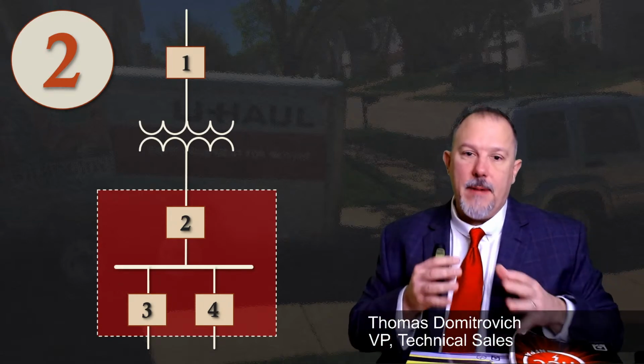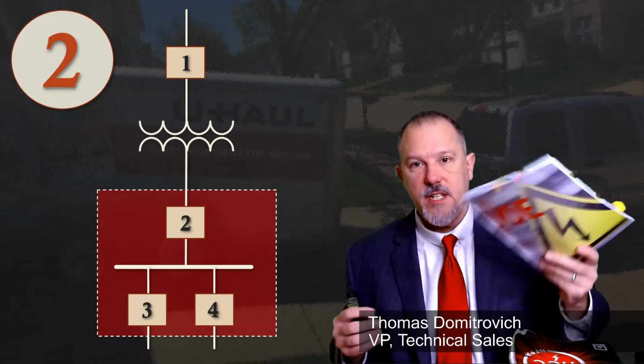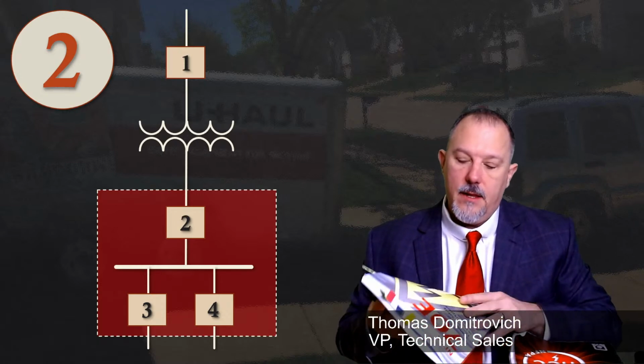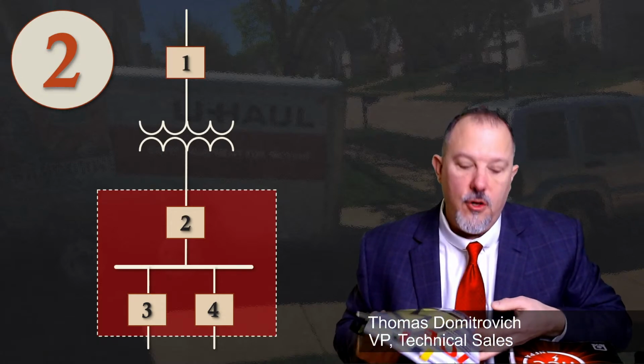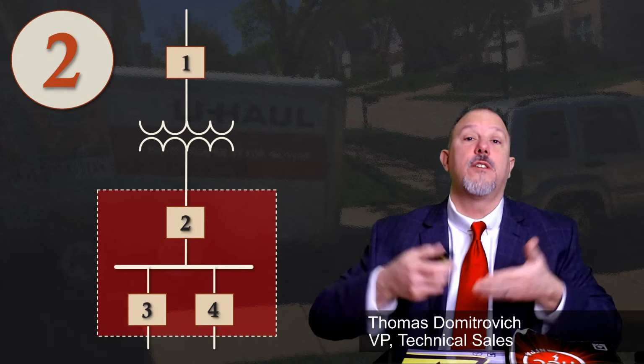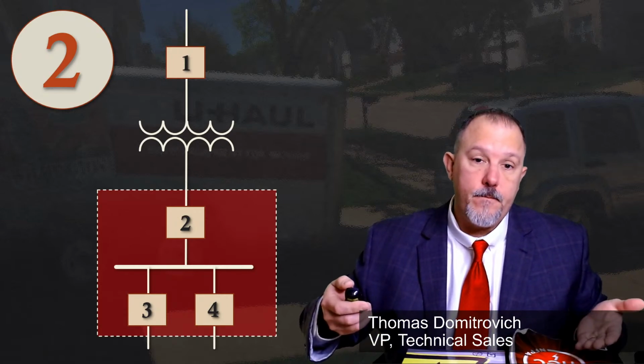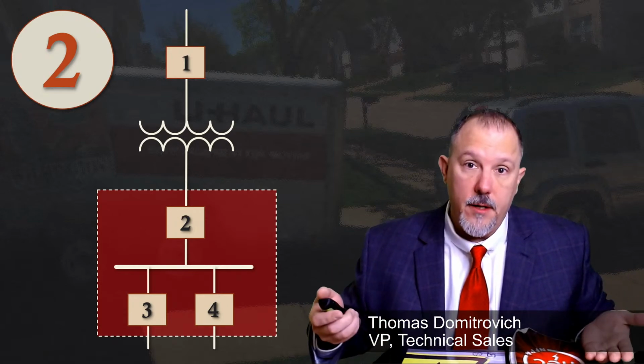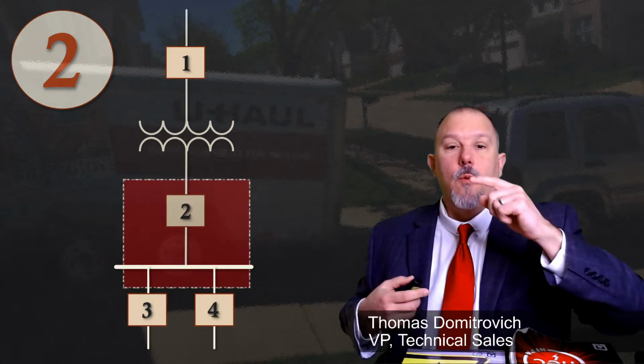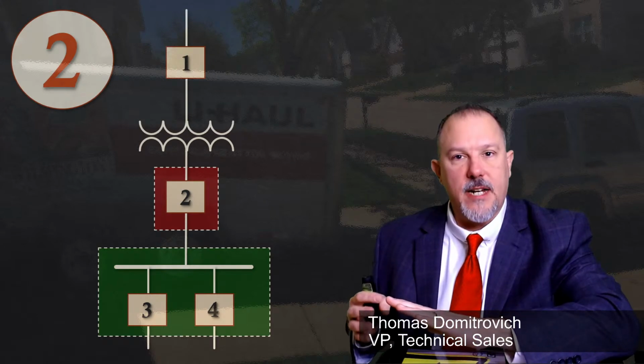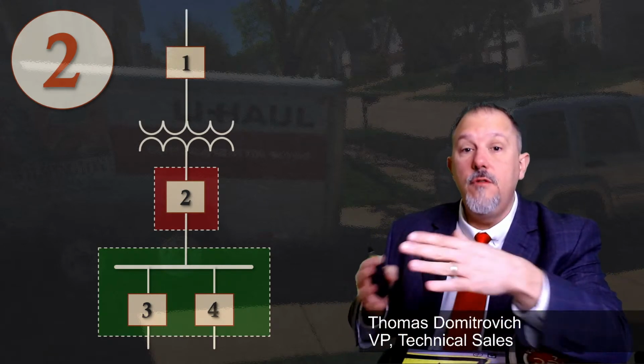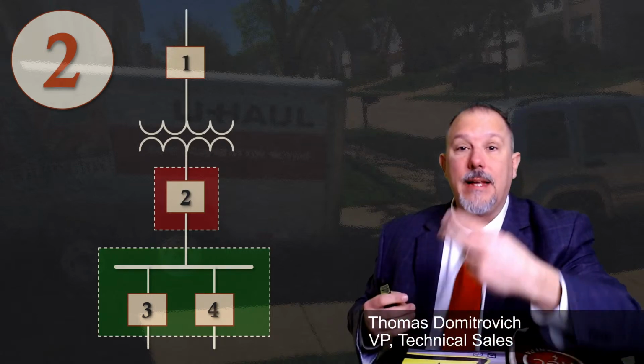And if you think about safe work practices, one reason you might perform justified energized work is to conduct troubleshooting, right? So what we said was move the energy: take that main overcurrent protective device, you could leave it in that enclosure if you want, or move it out and put it next to the equipment. What does that do? It does two things.